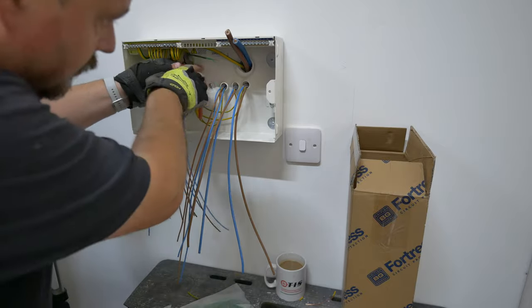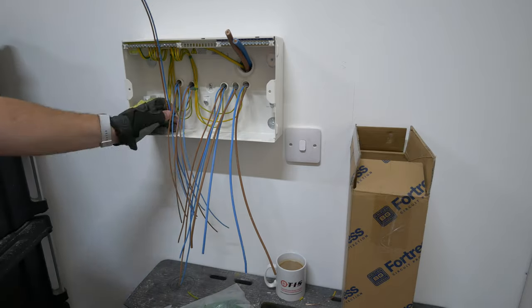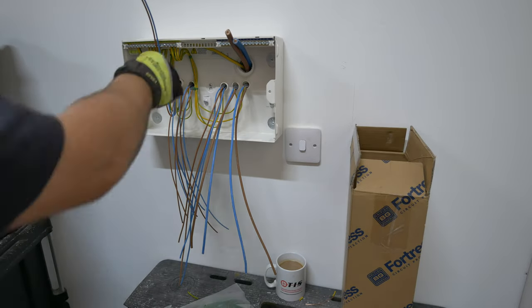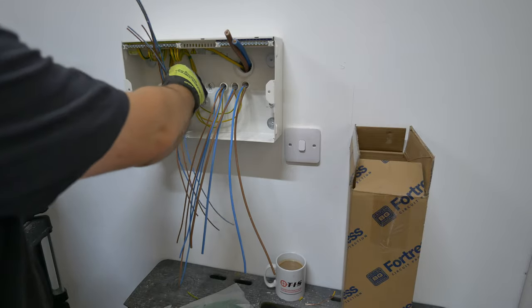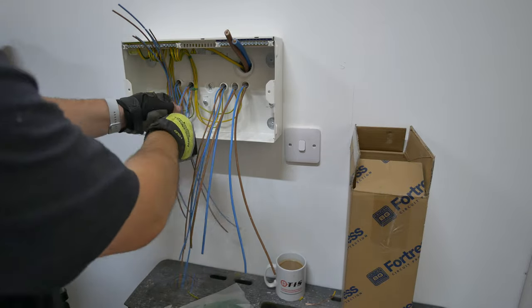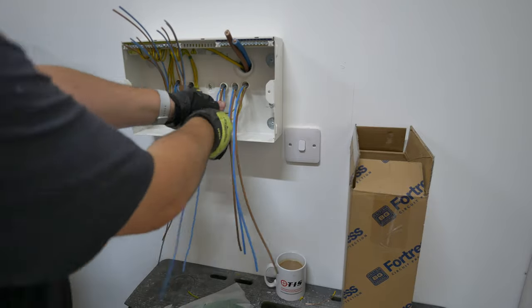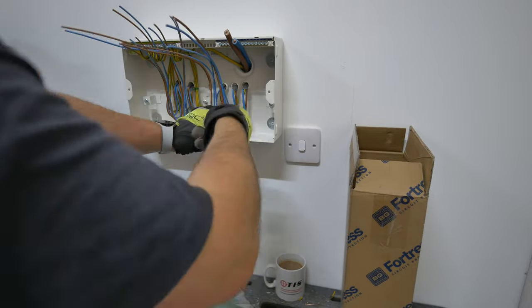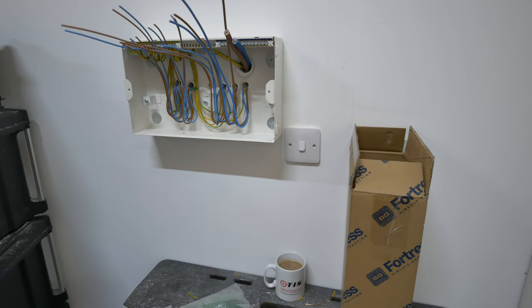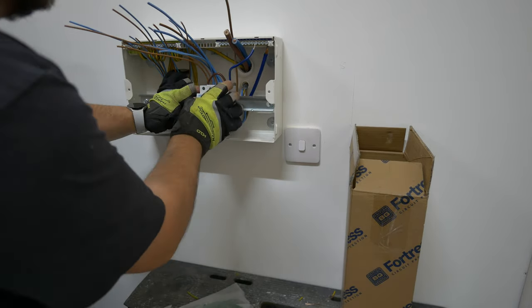I usually use cable ties to set things into position and then cut them off at the end - gives things a better prospect of staying neat and tidy. Speaking about the overheating aspect - if you've got containment leading up to your consumer unit generally all of the derating has been taken into account because of that, because a lot of cables when they're in horizontal trunking will naturally lay on top of each other. And if you've got circuits under continuous and simultaneous load then you will have to apply those derating factors. If those things don't apply then you don't need to worry about it.